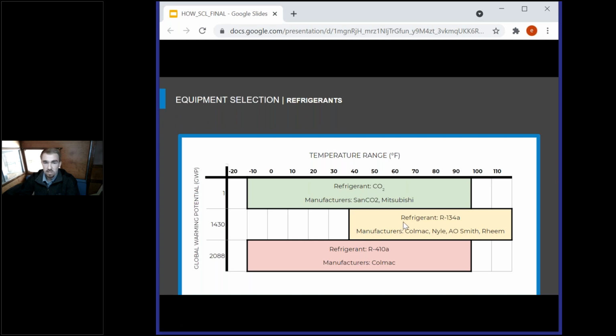And the solution in Seattle has been to put these R134A units in garages or conditioned spaces that don't go below 40 degrees. And Colin Grist will talk about that in the engineering deep dive and how those garages allow the temperature to not drift below 40 degrees and allow for efficient and reliable operation of these R134A heat pumps.